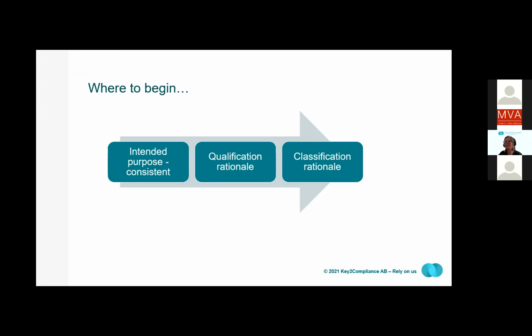Also remember that your intended purpose needs to be consistent through your documentation. The intended purpose will need to be the same as stated in the IFU, in the device description, or in the clinical evaluation. And this is because your intended purpose will, as mentioned earlier, be fundamental for your technical documentation. Also, think about that it's important that the intended purpose does not list claims with your device that are not supported by the clinical evaluation. For example, it's a very big difference between to diagnose something or to aid in diagnosing.